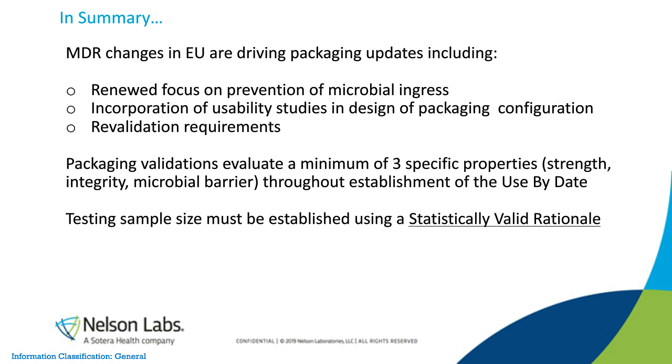Any changes in your SBS, your equipment, your processes, etc., you must consider and evaluate if any additional testing is needed. The question to always ask when you're looking at that is, did this change impact the completed validation testing you have on file? If it does, then it is very likely that testing will be required.